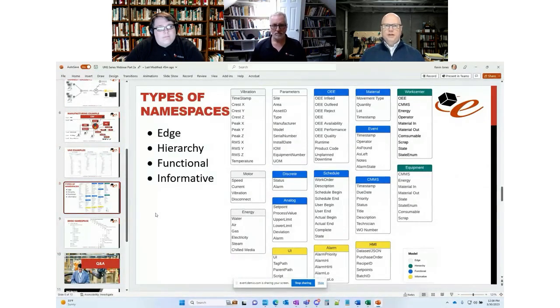So within the edge namespaces, sometimes I'll call this an asset or an equipment. So these are some of the models that we built during our last demo. People have a pretty good understanding of what these look like. This is largely going to be comprised of the tags that are included within your PLC or whatever your control system is. And it's that raw data, things that are changing all the time. So what I have examples of here is, I always like going back to my motor and pump example. So you're going to have data that's coming from your edge namespace, and you're now going to compile it or get it put together in a semantic data model. So instead of having raw tags, let's bring it together so we at least understand what is the asset, what is the equipment, what does this edge namespace look like.